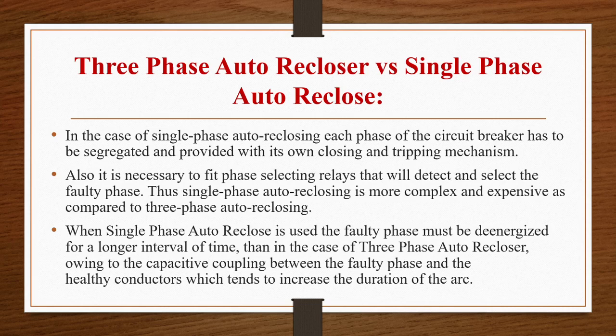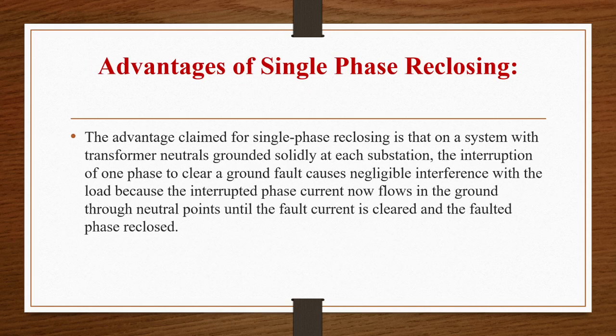When single phase auto reclose is used, the faulty phase must be de-energized for a longer interval of time than in the case of three phase auto reclosure, owing to the capacitive coupling between the faulty phase and the healthy conductors, which will tend to increase the duration of the arc.